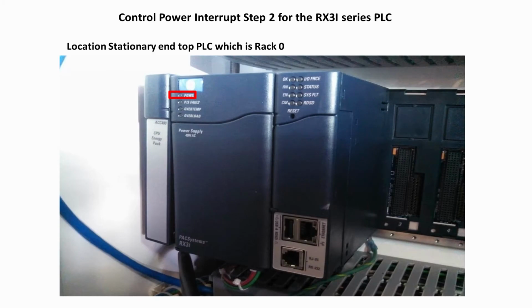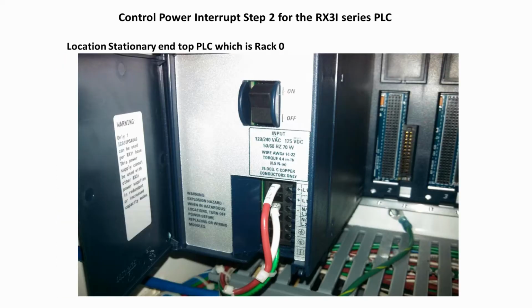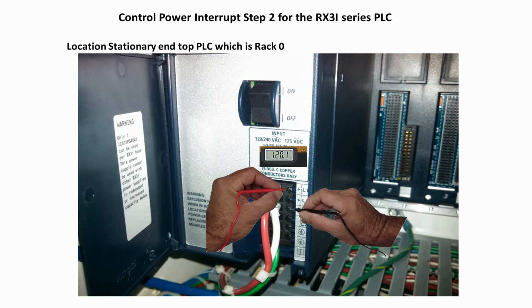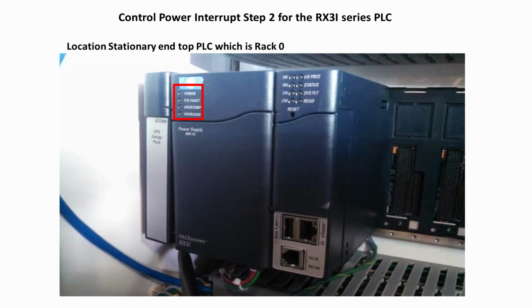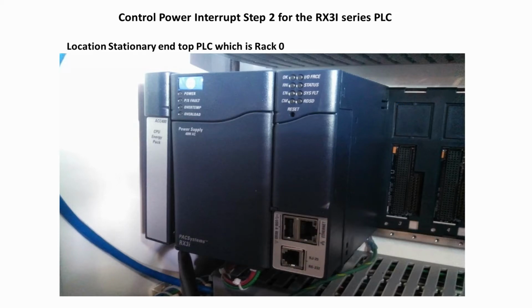Control power interrupt, Step 2 for the RX3i series PLC. Quick check number 2 is if the RX3i power supply does not have any lights on. First, open the door on the power supply and make sure the on-off switch is in the on position. If it is in the on position, then check for 120 volts. If you have 120 volts, then replace the power supply. If the power light is on with other lights lit on the power supply, then contact the Machinery Customer Service Department at 1-800-523-3380.